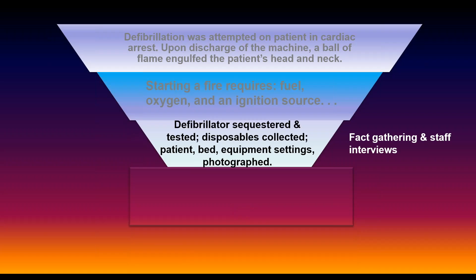But little by little, we had all of the information together, and what I was able to reconstruct with a Resusci Annie is that, first of all, this patient was a real big barrel-chested dude. He went into cardiac arrest, and the first thing nurses do, they'll lower the bed so they can facilitate chest compression. Well, they lowered the bed, but it wasn't down all the way. We had evidence of that. The nurse that went to defibrillate the guy, relatively short-statured nurse. Wasn't her fault, but she wasn't able to make good paddle contact here. These older Lown defibrillators, this is an old HP at the time, old Lown defibrillators, peak open circuit voltage 5,000 to 7,000 volts, not uncommon.